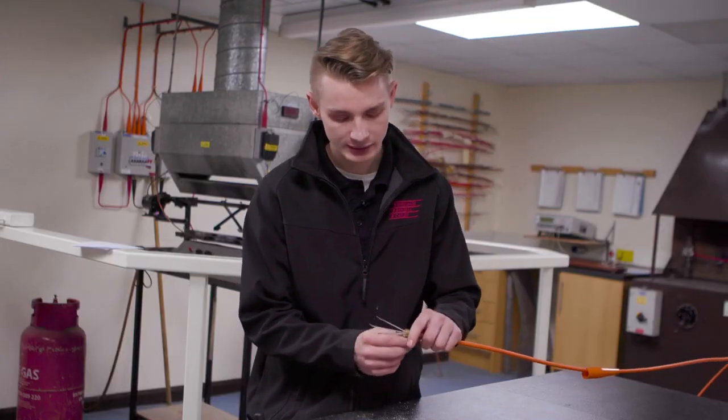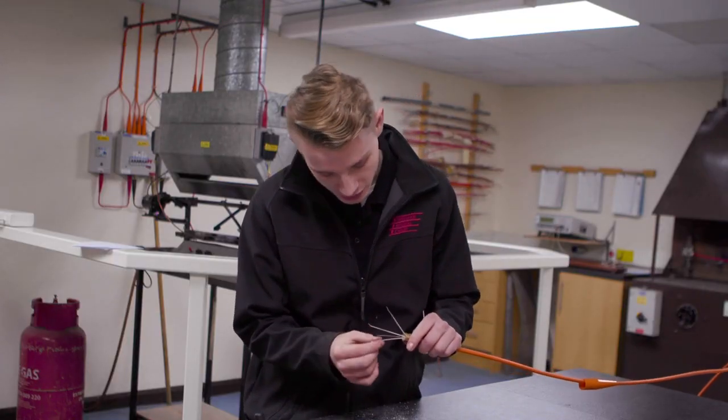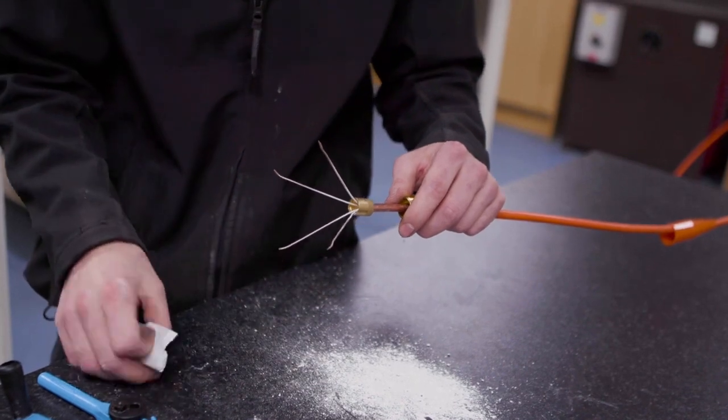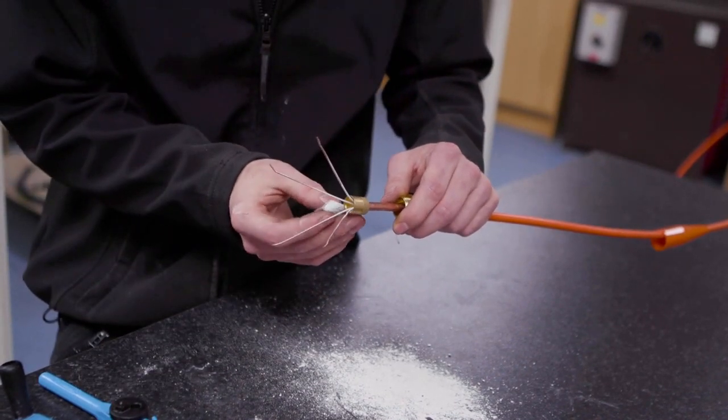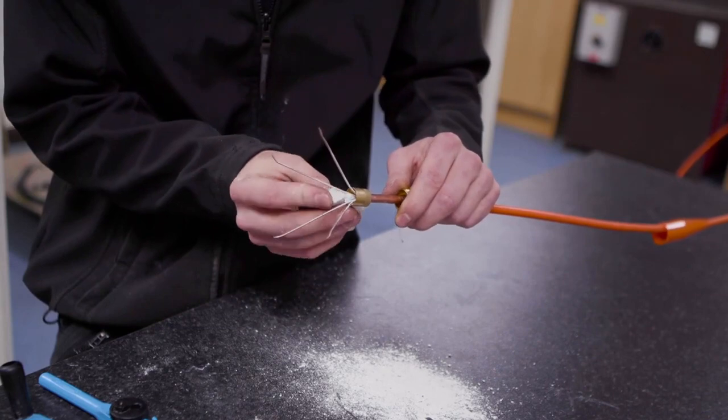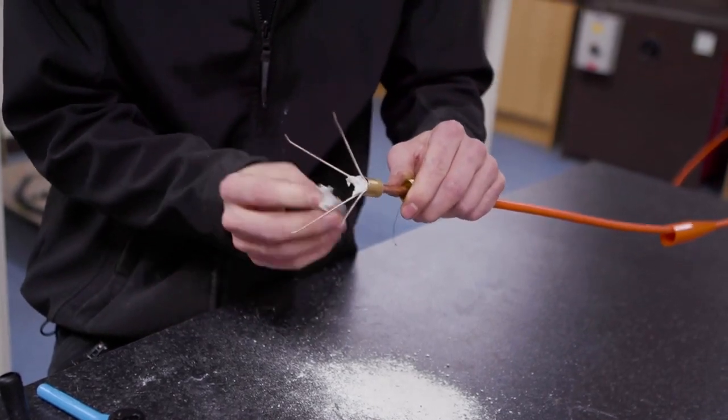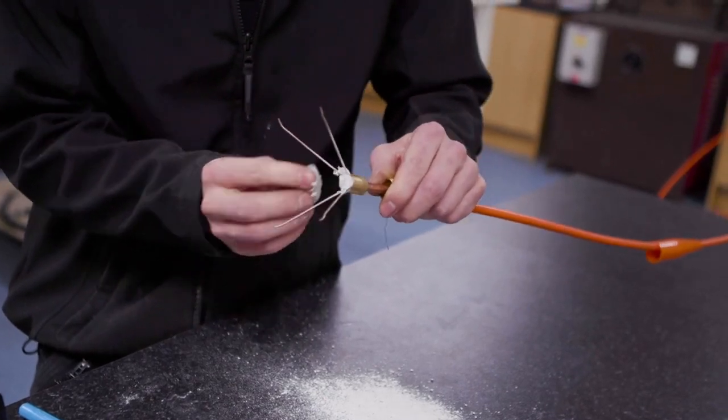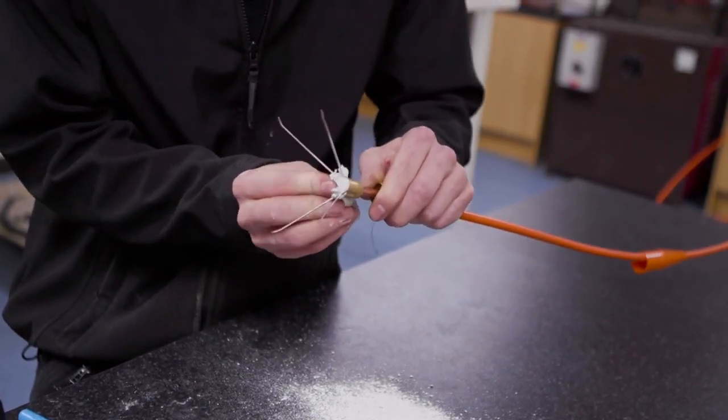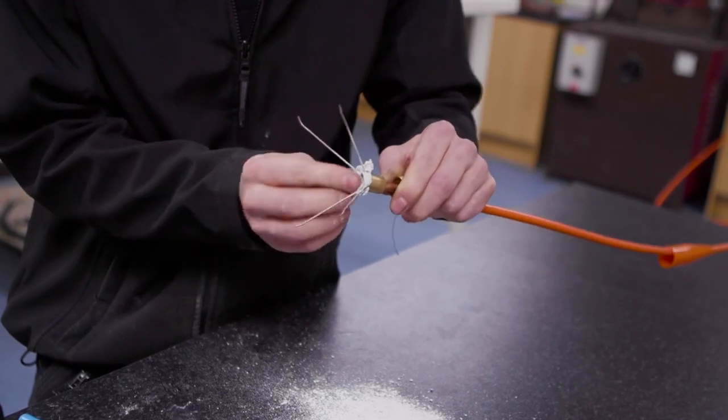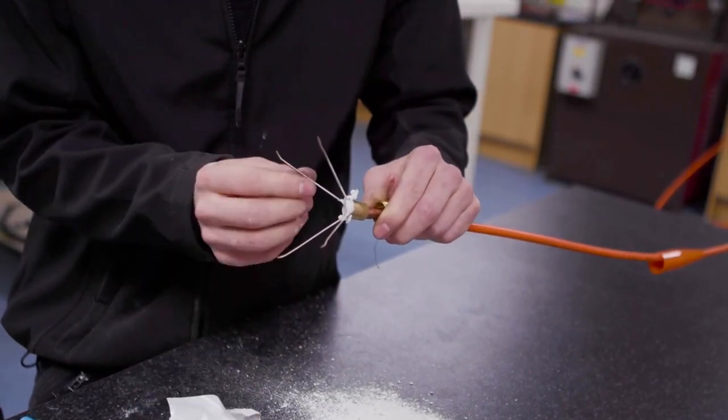So our next step now is to spread the conductors out, making sure that none of them are touching. Then we'll apply the compound from one side only, making sure we push it all the way down into the base of the pot until it starts coming out of the other side so we know that there's no air locked inside of the pot.